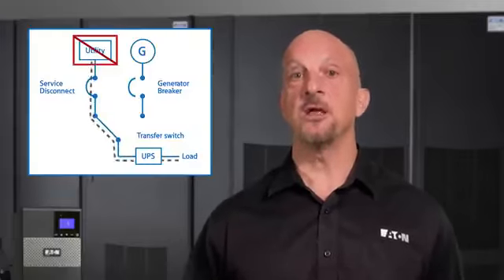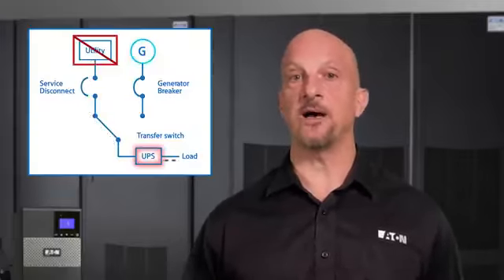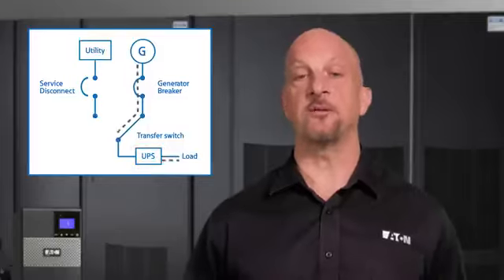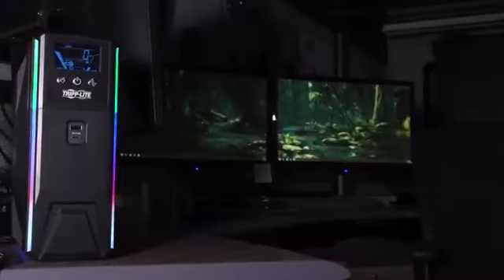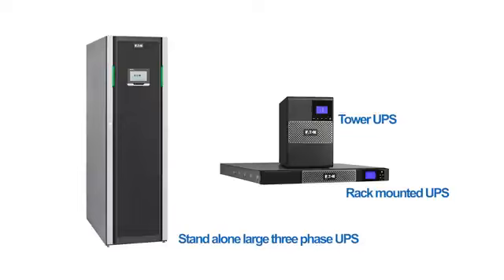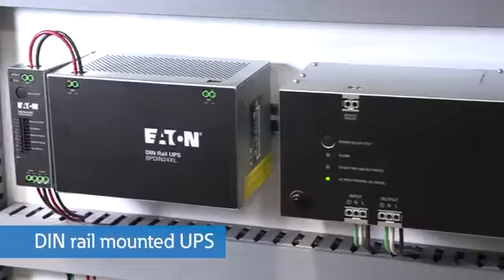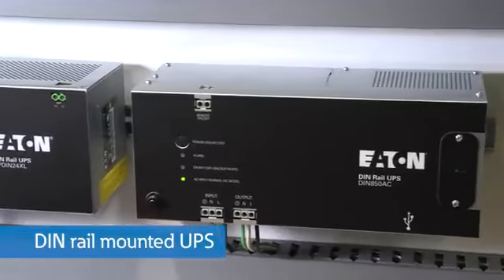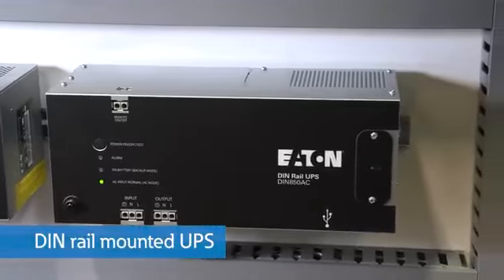For larger systems, most times the battery duration must simply bridge the gap between the power outage and the startup of a standby generator. Today, for special applications like e-houses, machine builders, or even gamers, we have a lot of variations in these UPSs to choose from. Some of these UPSs have a different form factor, like the DIN rail mounted UPSs and 24-volt battery backups that machine builders use inside control cabinets or MCCs. But essentially, they're all variations of the 3 basic UPS types.